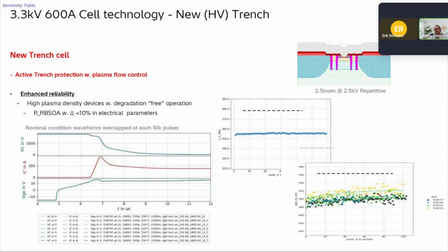We apply 100,000 pulses under these SOA conditions and look at the turn-on event, the waveforms, and the difference in DI/DT and DV/DT. If we saw degradation of the gate dielectric, especially at the bottom of the trench, we'd get a change in the gate dielectric and through that a change in capacitance and how the IGBT turns on, affecting DI/DT. That's not immediately dangerous, but it puts more stress on the diode over time and can eventually lead to failure. So an internal figure of merit is running at least 100,000 such SOA pulses and checking the turn-on DI/DT as our limit.